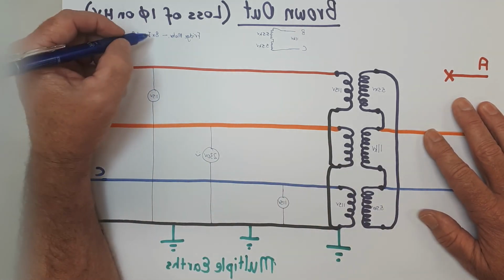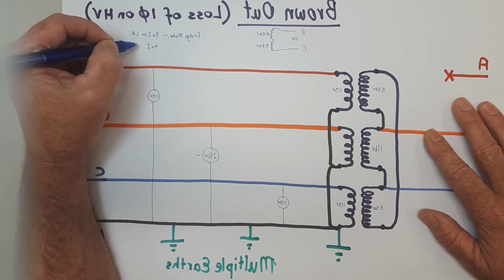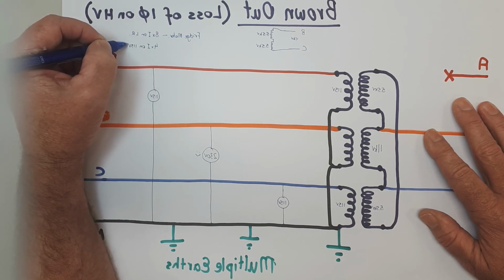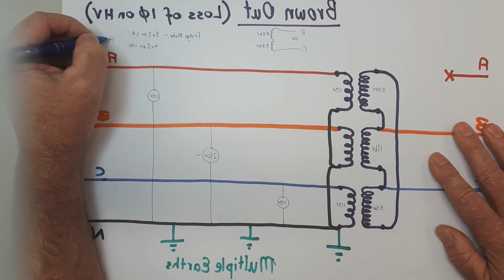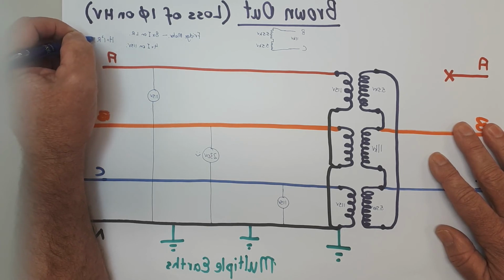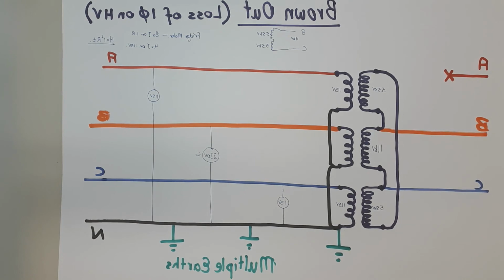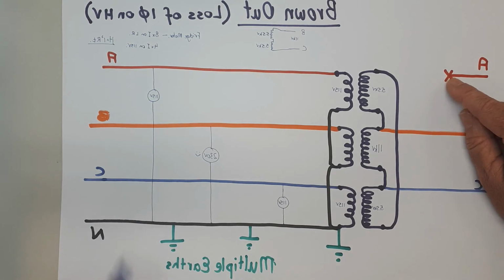Still, that's not enough torque to start the motor, so you're down to 4 times current on 115 volts. And with the 4 times current, remember that your heat is I squared R T, so it's sitting there, it can't start, it's got 4 times the current, which is 16 times the heat. So that's what happens to fridge motors sometimes in a brownout. They're on half volts, it's not enough volts to start it, but it's enough that it's sitting there on 115 volts on locked rotor, and it burns out. So that's how it happens. That's one of the ways, a common way to have a brownout: to lose a high voltage phase and 2 of your low voltage phases go to half. Half or approximately half. It's not exactly, it depends on how the load is shared between the phases, but that's the theory on it. So that's your brownout.